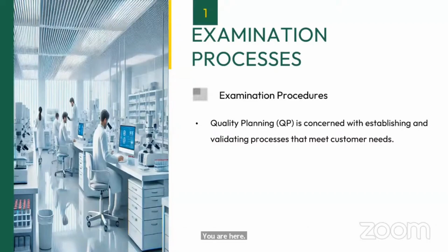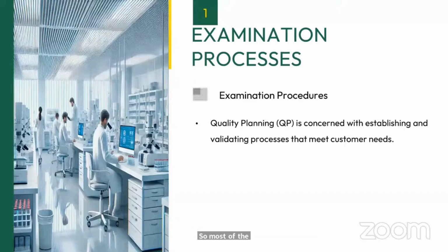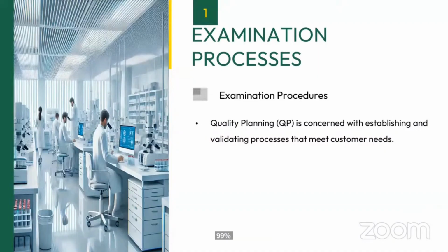Is anybody doing this validation? Are you developing any new methodologies in your laboratory? So most of the time, 99% of the time, we are not developing any new method in our laboratory. We are using those methods which are IVD approved, which are well validated. We are just using those methodologies in our laboratory. So we need not perform any validation. 99% we are using already validated methods. So the only thing you have to do in your laboratory is the verification.